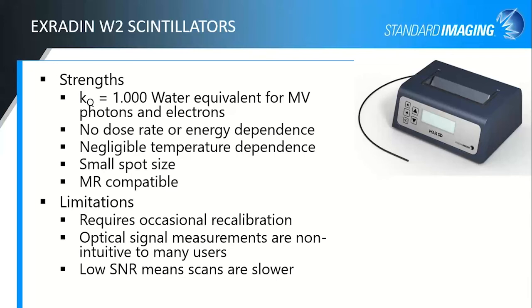Another of the limitations is that we've discovered optical signal measurements are not really intuitive to most physicists yet. We're used to ionization chambers and we're used to diodes, and so troubleshooting what's wrong with a scintillator has been a little bit trickier for them. But once you get used to it, it's quite easy to use. The other limitation of the W2 is that because of the low signal and the low SNR, you have to scan more slowly. So we usually recommend you do a 1 second measurement at each dwell point for your scan. This is a small field scan. It's totally worth waiting the time to get that good data and not have to smooth it and correct it and do other processing with it.